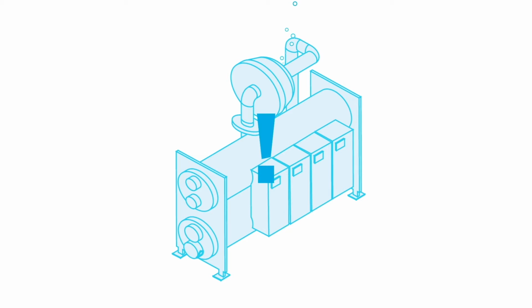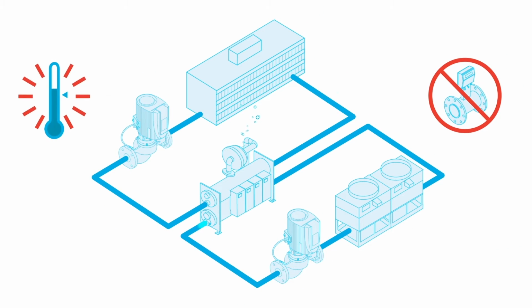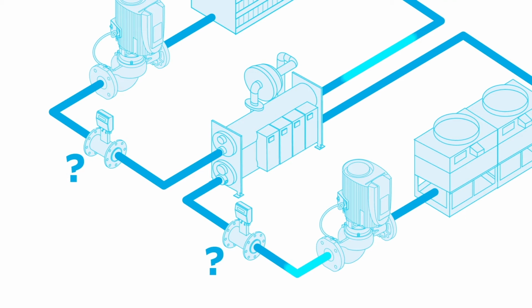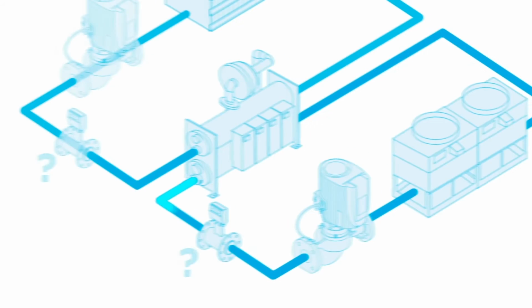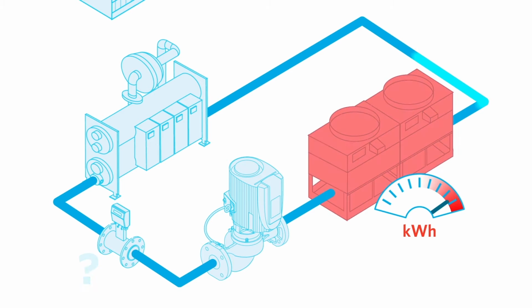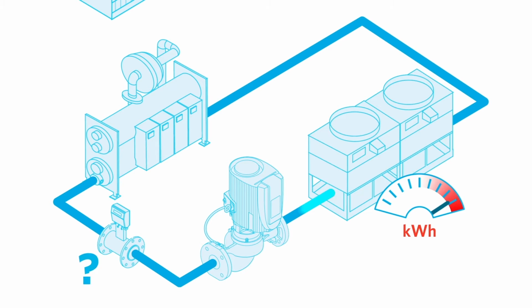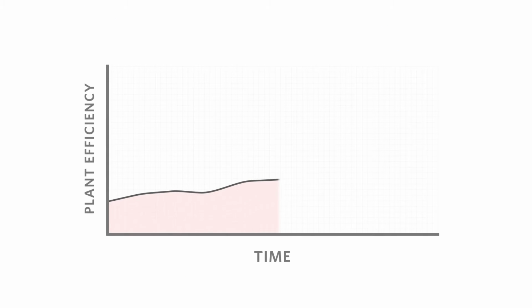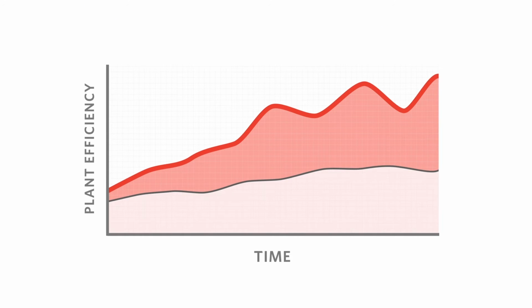The building operator is often unable to identify progressive degradation hidden in the HVAC system. Without a flow meter installed, issues are identified only if the temperature set points in the system cannot be maintained. By then, it's too late, and after months of inefficient operations that could have provided a warning signal, occupant discomfort becomes a problem. Accurate flow meters are rarely in place in HVAC systems and are almost never installed on all of the circuits necessary to calculate heat balance. Particularly in a cooling tower or condenser circuit, where water circulates between the chiller and the cooling tower, the efficiency of heat rejection is rarely known or even tracked. Even for those rare cases where a flow meter was installed, if it is not maintained and recalibrated, flow data becomes unreliable. As a result of this low accuracy, undetected system performance drift is common.